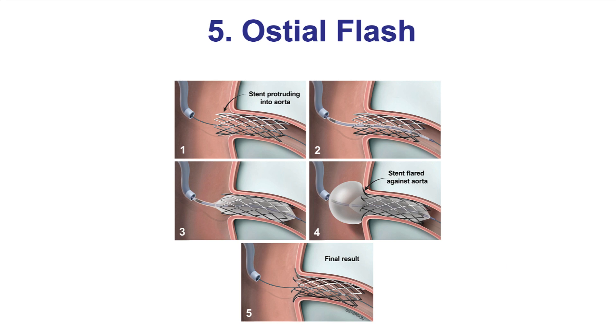Number five type of balloon is the Ostial Flash balloon. This is a unique balloon — it is actually two balloons combined. There is a more distal balloon that is sized one-to-one with the proximal vessel, and then there is a larger balloon that inflates at low pressure, up to eight atmospheres. What this balloon does is it flares the struts of the stent against the ostium of the stent, making repeat engagement of that vessel easier and preventing the stent from protruding into the aorta and hindering repeat engagement with catheters.